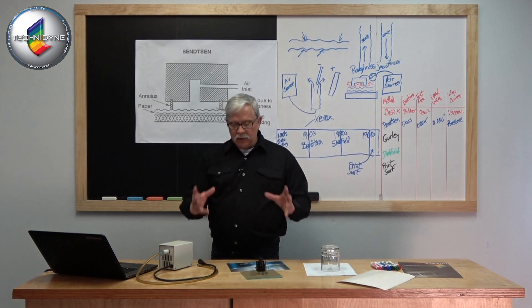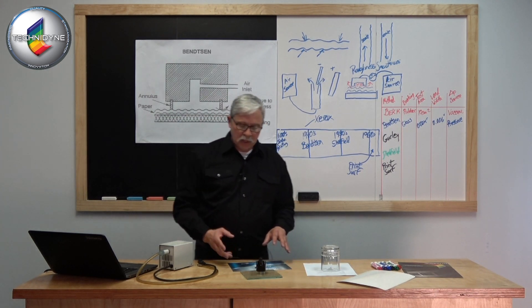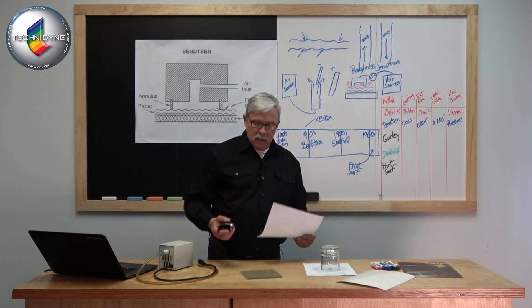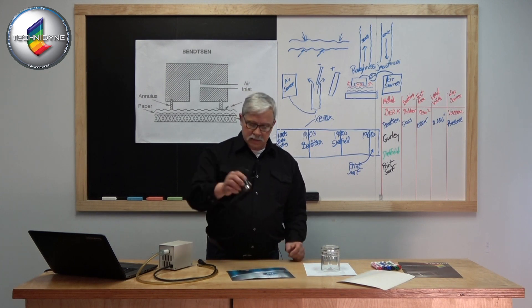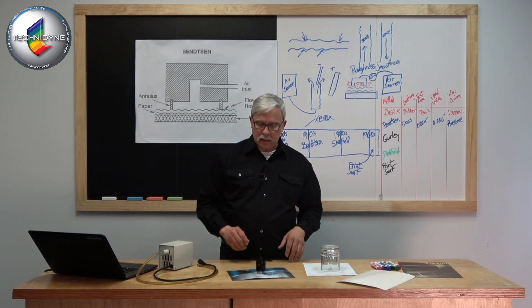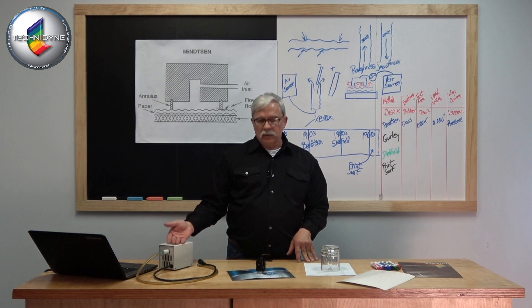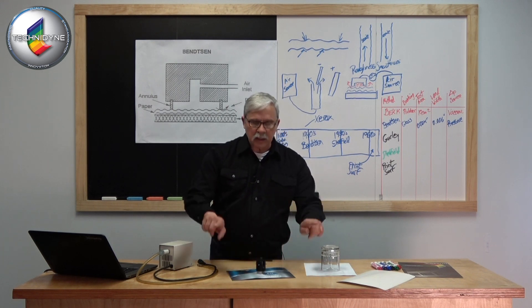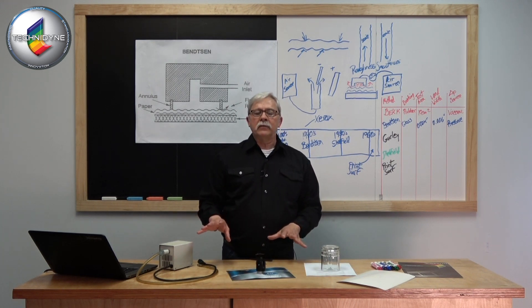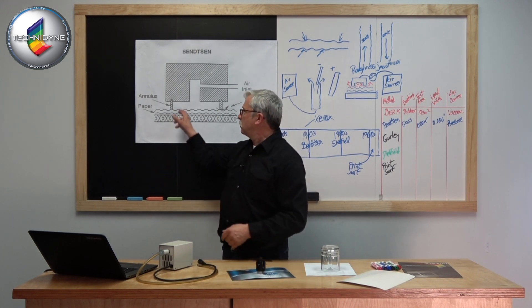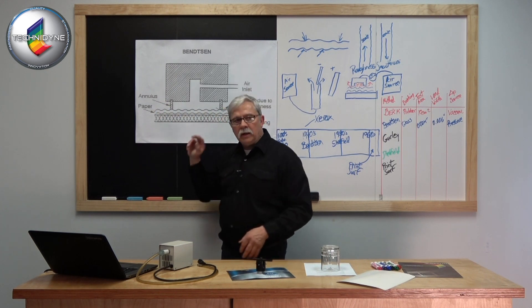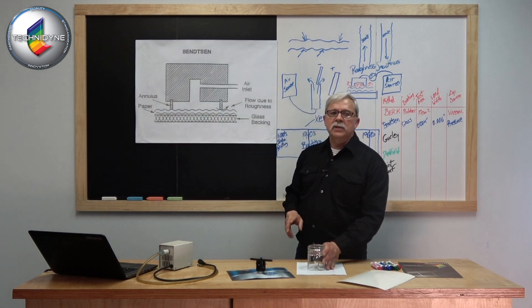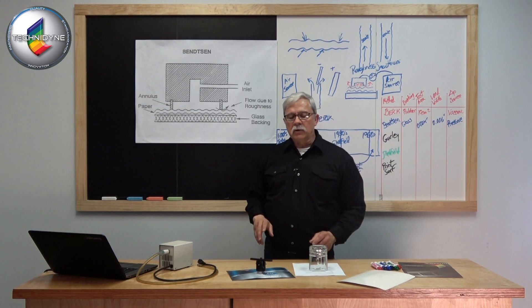I have all these pieces put together. Now I can take my sample, lay it on the glass, place my measurement head on, flip my switch so I have my air compressor running. I have air going to my measurement head, air leaking out, and now I can measure the amount of air that escapes underneath the annular ring due to the topography of the sample.